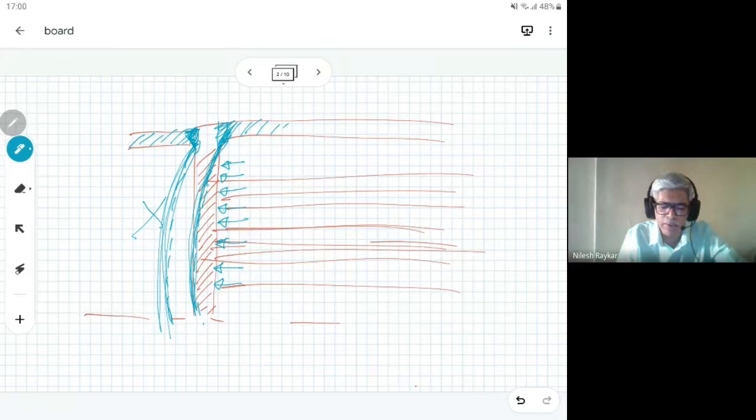If you consider that these tubes are helping the tube sheet not to bend, then the load has to be taken by the tube to tube sheet joint, which the designer doesn't consider. The tube sheet is designed such that, without the help of tube strength, the tube sheet is okay.